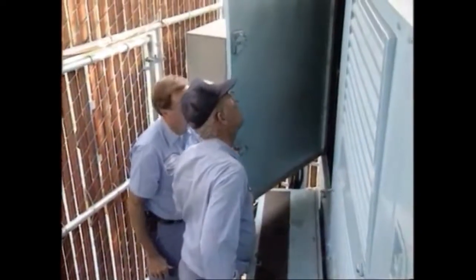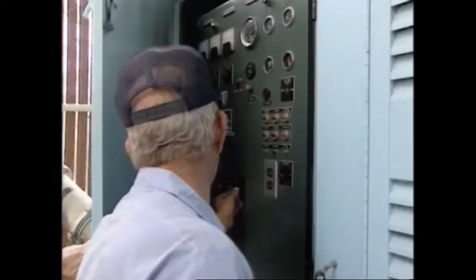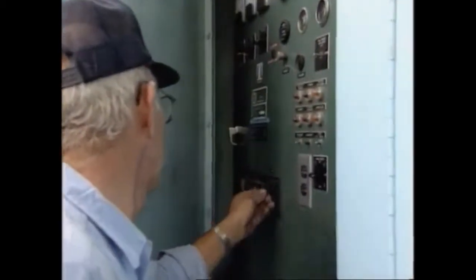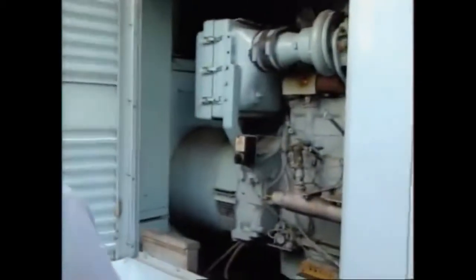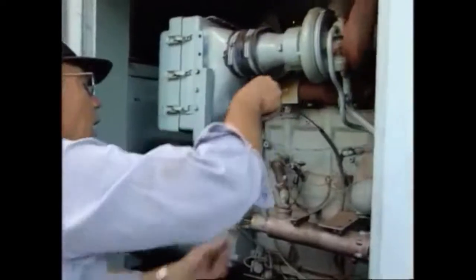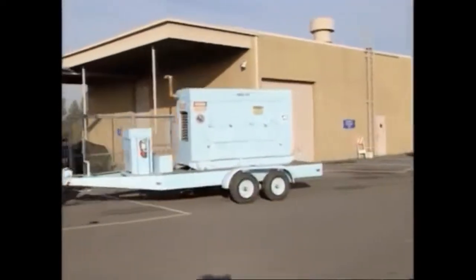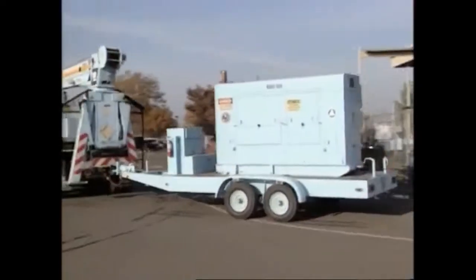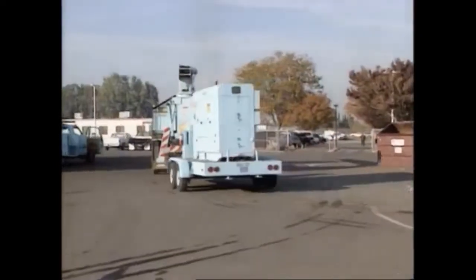Works for me. Remember, if your pump station's downtime is under an hour, we have a serious problem. Certain decisions must be made, either to install larger pumps, or if money and space are available, install a larger wet pit. Another good idea is an emergency response plan for each lift station. If power failures are a problem, an emergency generator should be installed to operate the station during power failures. Other solutions to power failure include portable generators, 2 sources of utility power, or engine drive pump.